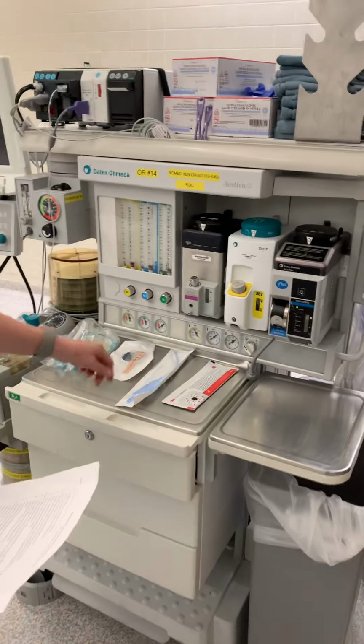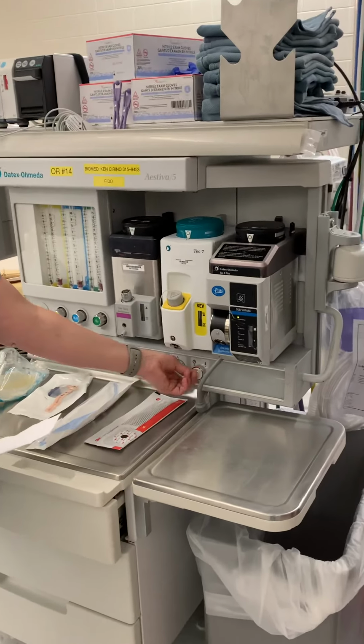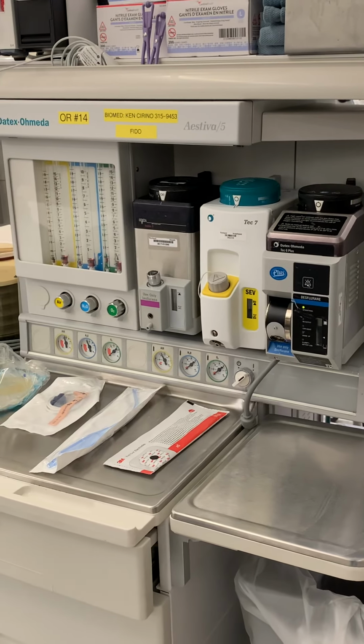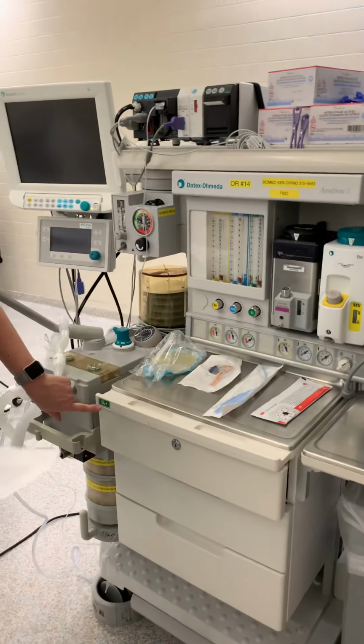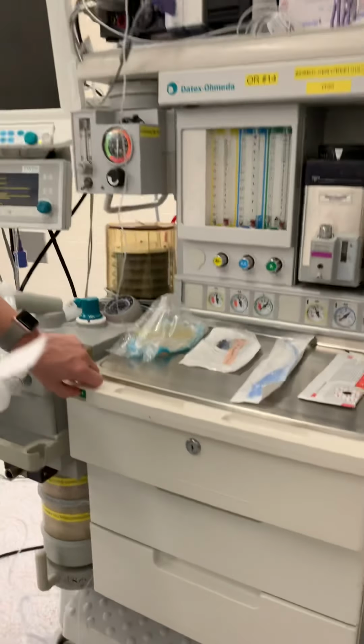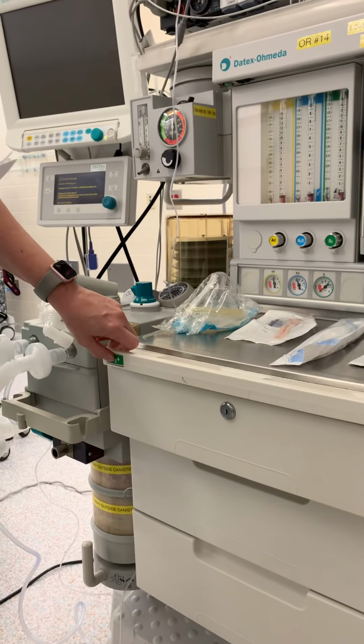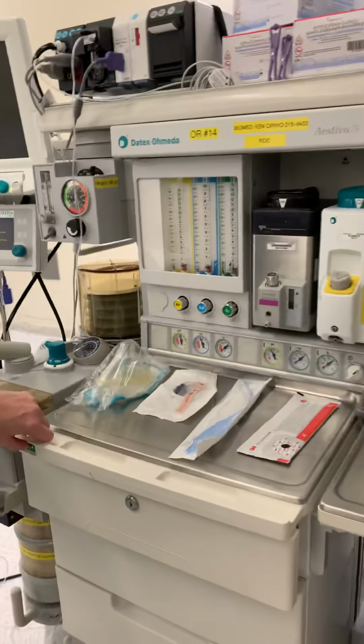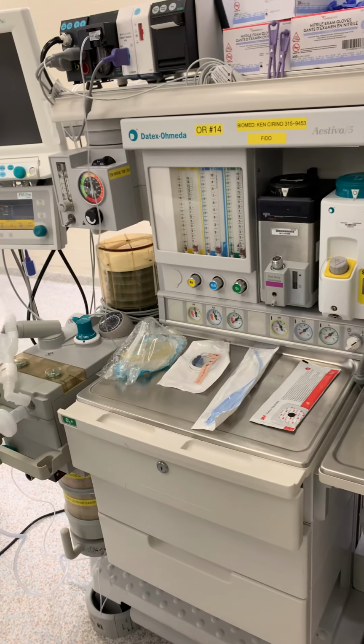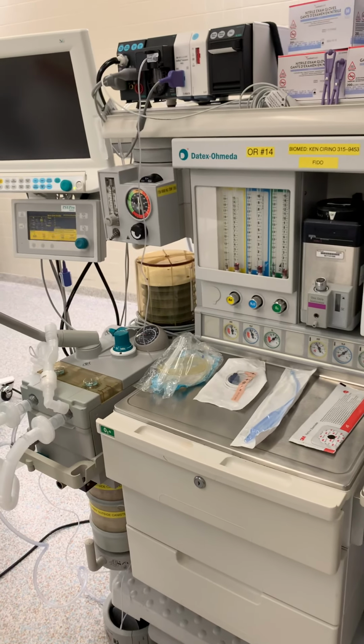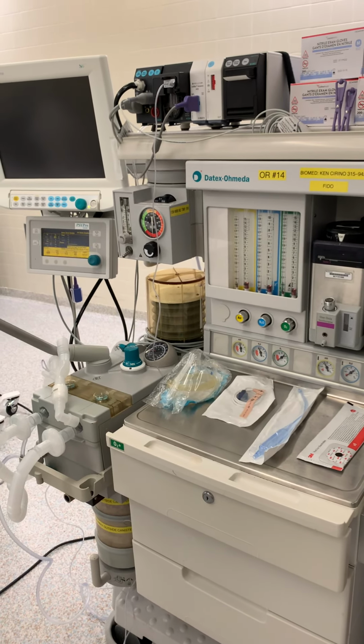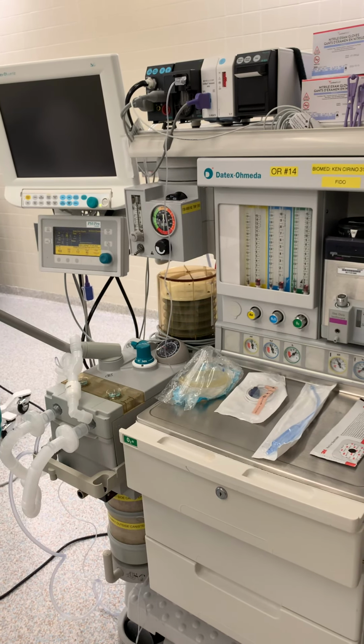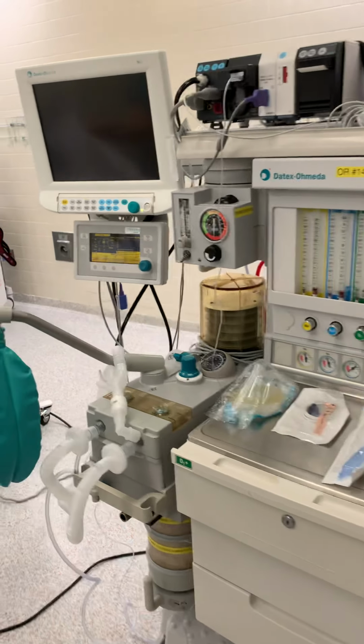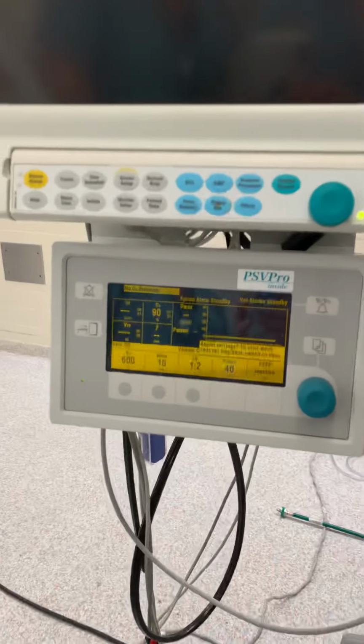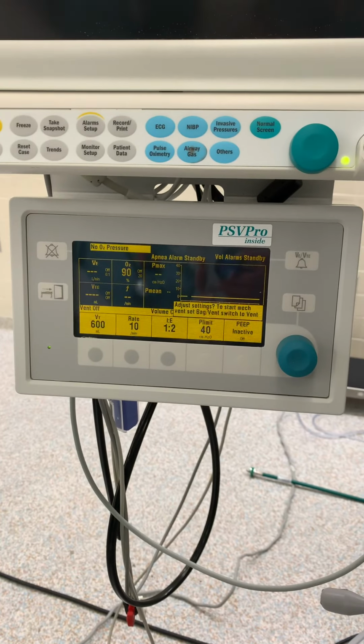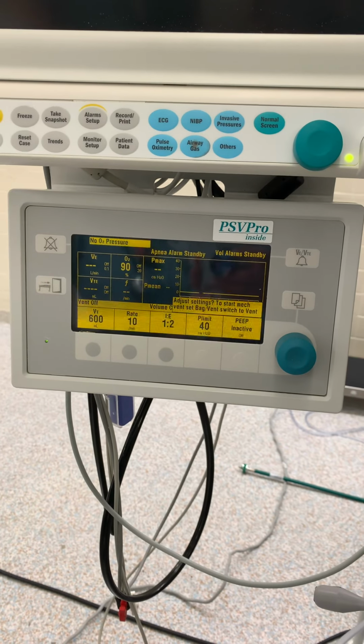Now what you're going to want to do is turn the machine on. And once the machine is on, we're going to push the oxygen flush valve, and what we're doing is just bleeding the machine of any oxygen, because we now have no oxygen source, and we're listening for the alarm that's going to let us know that we have no oxygen coming to the machine. That's a very important alarm. And you can listen again to this very distinctive sound.